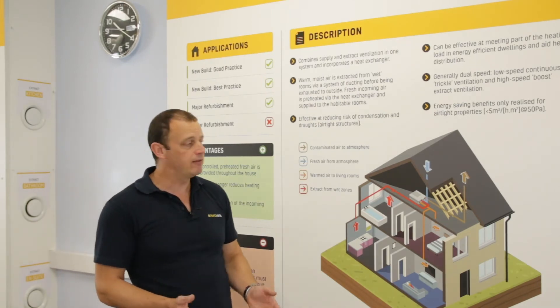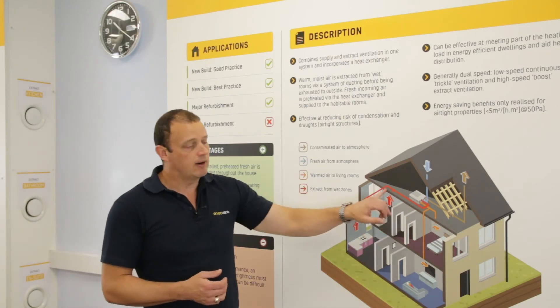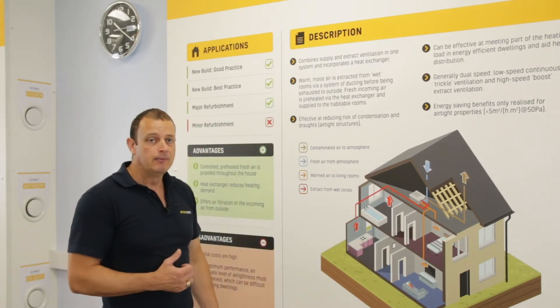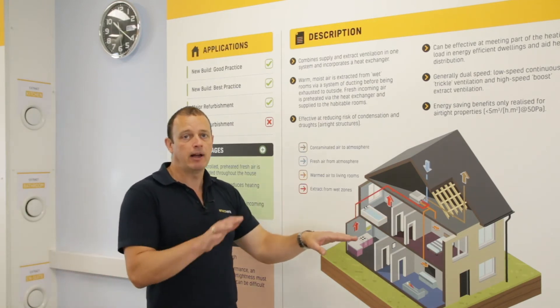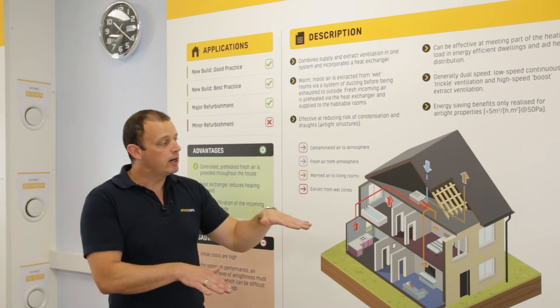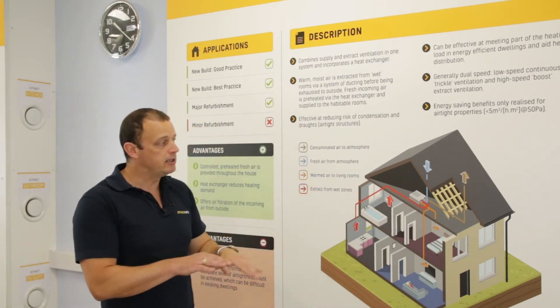It does vary on the unit and also on your air flows and atmospherics. As a guide, that's what you're going to be doing. It is very partial to a good install - you've got to have a good install to get the full benefits. You do have a lot of ducting to run because you have to ventilate each room - extract from every wet room: kitchen, en suite, bathroom, WCs, utilities - and supply air to every habitable room. That ensures you get the full heat recovery. We also keep the air flows balanced: whatever total we take out, we bring in as a total. If the system is imbalanced - say we took out 50% more air than we bring in - we actually reduce the efficiency of the heat cell by 50%, so instead of being 90% efficient it might only be 45%. So it is important we keep a balanced system.